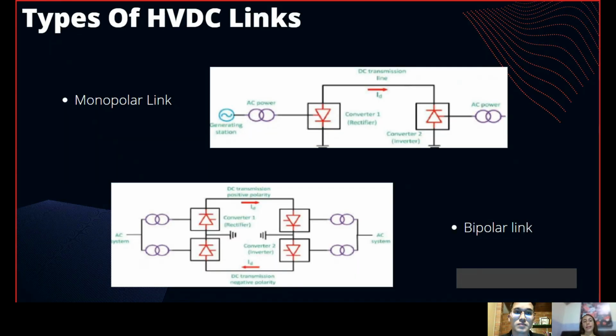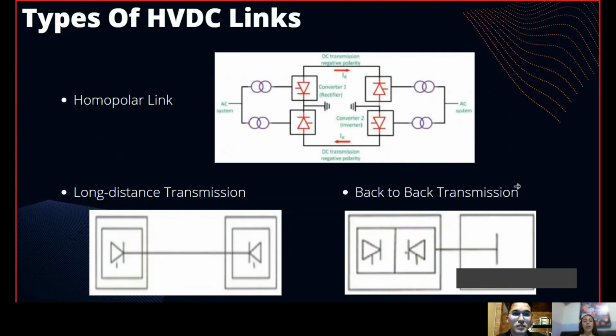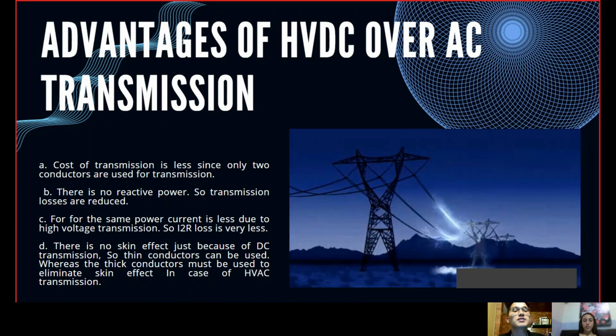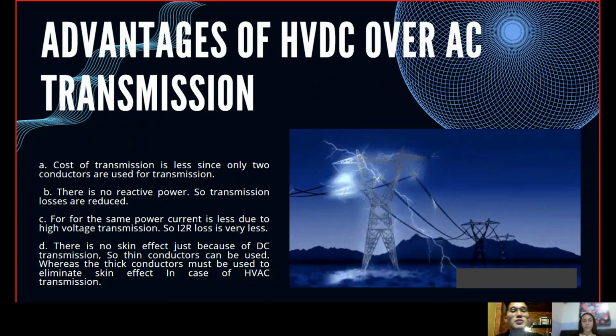Types of HVDC links. Generally, there are three kinds of HVDC frameworks. The determination of every structure in the planning stage rests upon the operational prerequisites, the adaptability of the demand, the issue of consistent quality, and the cost. The most well-known HVDC designs are as follows: monopolar link, bipolar link, and homopolar link, long-distance transmission, and back-to-back transmission. Advantages of HVDC over AC transmission.